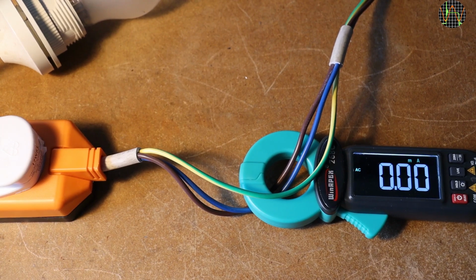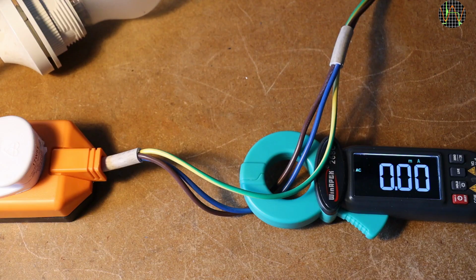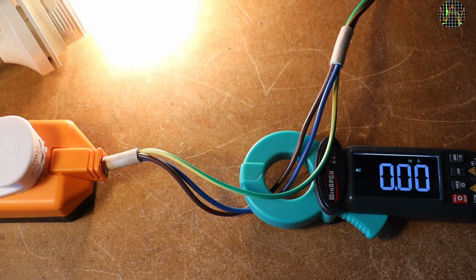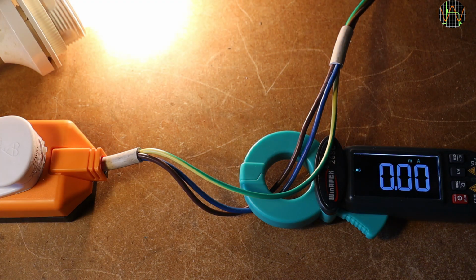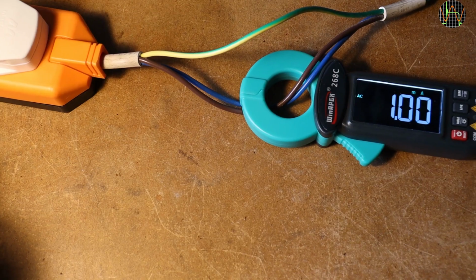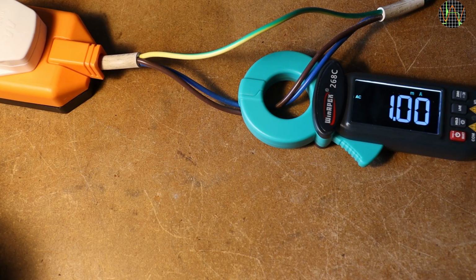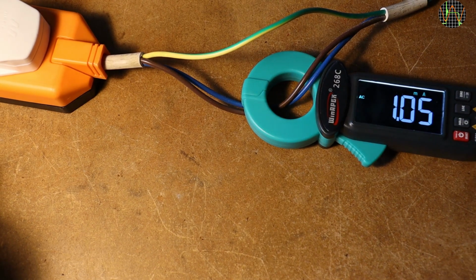So, for example, does this simple incandescent light bulb contribute any leakage? The answer is no, and there isn't really anything here that could, but you will find that a lot of things in the house have a bit of leakage, especially things with mains filters or surge protection. Here, for example, is an imbalance of 1 milliamp, but as there are several devices connected, I can make that larger by turning more things on.